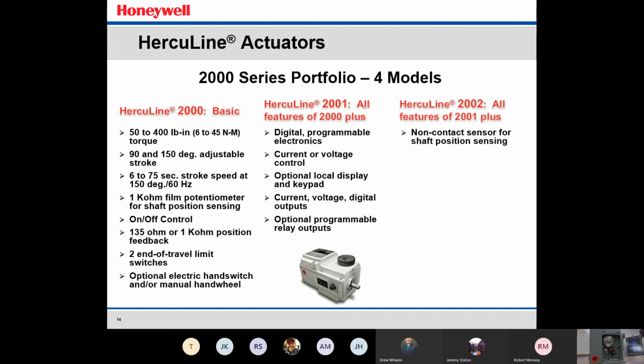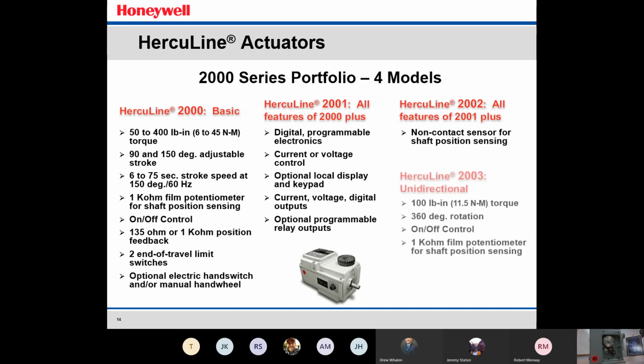Last but not least, we have the Herculine 2002. So it has all the features of a 2001, but it also has a non-contact sensor. So we talked a little bit about this, and both actuators have the option for non-contact. And then on the 2003 model, this is the unidirectional model, which only offers up to 100 inch-pounds, 360-degree rotation, and just an on-off input. This particular one, like I said, is not used widely out in the industry, but if you do see some surface combustion integral quench furnaces, most of the time you're going to see this actuator mounted on the damper shaft of the exhaust coming out of the oven.